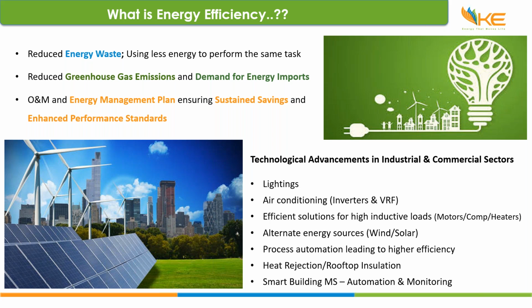For high inductive loads like motors, compressors, and heaters, efficient solutions are available like VFDs and harmonic filters to minimize harmonic losses. VFDs allow operating the same rating motors at the required RPM. The fourth area is alternate or renewable energy, like wind and solar, if an industry or commercial sector has provision to install it.